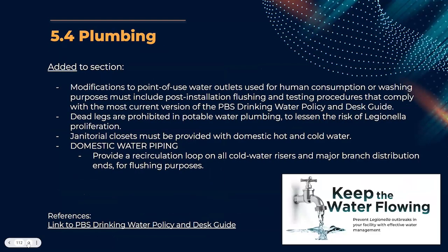Next slide, please. There's been a lot of new requirements added to the plumbing section. Just to summarize a few, there's added guidance on flushing procedures for newly installed domestic water systems. There are also new requirements to provide recirc loops at the end of all cold water risers and major distribution to encourage flushing. And isolation valves are required on all branch distribution in rooms that contain more than one domestic water fixture, such as bathrooms or other spaces that are off the core area. Hose bibs are to be provided every 100 feet along the building perimeter, and floor drains are required in all rooms provided with domestic water fixtures. Overflow pans are also required to be provided under domestic hot water heater storage tanks.